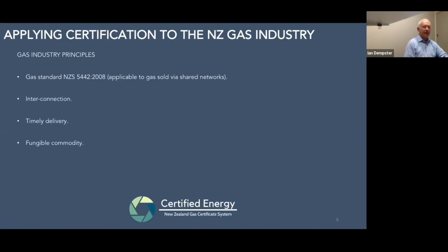Well, you'd have to have exactly the same requirement that a green gas producer only injects spec gas. That's a requirement under the gas safety and measurement regulations, and there is no exemption for that. So before you allowed somebody to directly inject into a distribution network, you would have to obviously arrange some certification of that. And actually, I guess the other thing you'd have to arrange is making sure that it was odorized.